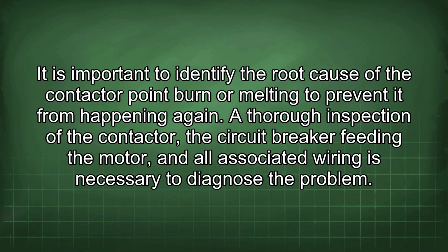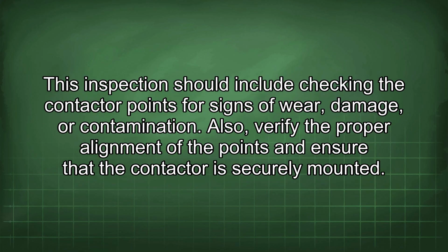It is important to identify the root cause of the contactor point burn or melting to prevent it from happening again. A thorough inspection of the contactor, the circuit breaker feeding the motor, and all associated wiring is necessary to diagnose the problem. This inspection should include checking the contactor points for signs of wear, damage, or contamination. Also, verify the proper alignment of the points and ensure that the contactor is securely mounted.